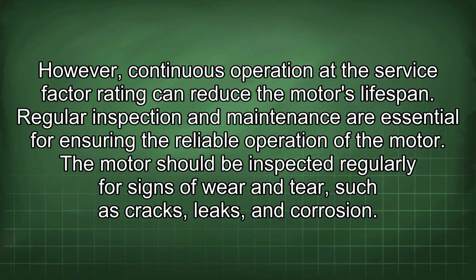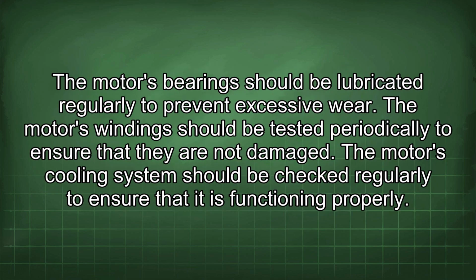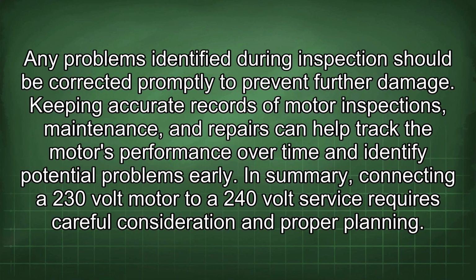Regular inspection and maintenance are essential for ensuring the reliable operation of the motor. The motor should be inspected regularly for signs of wear and tear, such as cracks, leaks, and corrosion. The motor's bearings should be lubricated regularly to prevent excessive wear. The motor's windings should be tested periodically to ensure that they are not damaged. The motor's cooling system should be checked regularly to ensure that it is functioning properly. Any problems identified during inspection should be corrected promptly to prevent further damage.